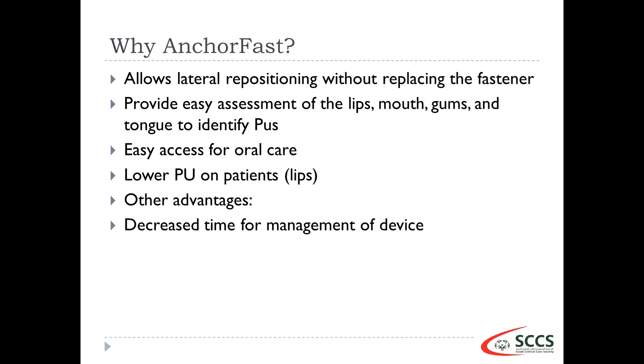Another reason is that there is easy access for oral care. There are also other advantages with the Anchor Fast: it can potentially decrease the time for management of the device. So it can potentially save the clinician time, because it's not going to require as many changes as the other devices do. With the twill tape and with the adhesive tape, they're going to require almost daily changes. However, with the Anchor Fast, the recommendation is to change it about every 4 to 7 days. So this is another advantage when considering using the Anchor Fast as an ET tube holder.